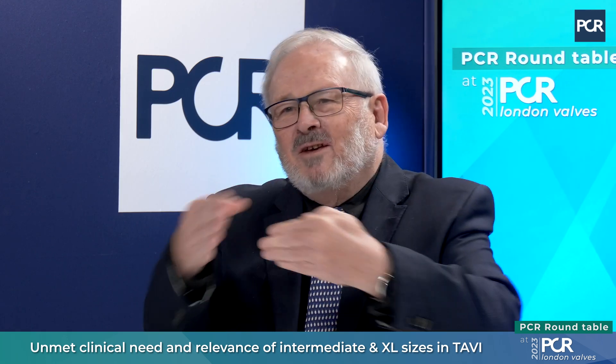Andreas, can you remind us what was the step involved for the surgeon with other technology, and what is the major step forward here? Here we've got 1.5 mm increments. The standard valve sizing for transcatheter valves is 3 mm — so that's double. The surgeons work on 2 mm differences. If you look at the mm squared area, the range will be 700 to 860 mm², and it's interesting that there is always some overlap. So you can eventually play a little on the downsize or upsize.